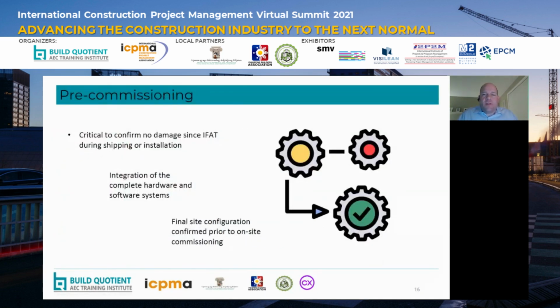So pre-commissioning is the next stage of the commissioning process, where we really pick up from what we completed during integrated factory acceptance testing. When the equipment is completed, IFAT, and everything is passed, and everybody agrees that the IFAT is complete, then the equipment is disassembled, all the cables are pulled apart, all the cubicles are packaged up in crates and sent to site. From that point in time when IFAT was complete and we knew that we had a functioning system, there's always the risk that something gets damaged during shipping and something gets damaged during installation. So during those two phases, we want to verify that no damage occurred, and pre-commissioning is the point in time when we do that. Once the equipment arrives at site and it's reinstalled in a permanent final configuration, pre-commissioning starts to verify that what we saw in IFAT is now what we also see during pre-commissioning on site.